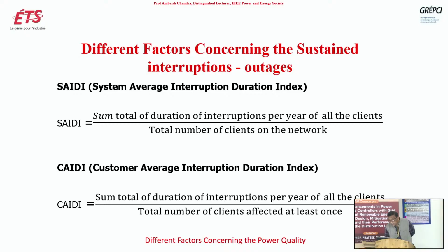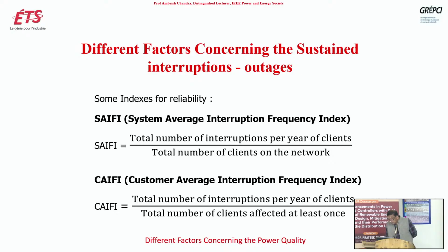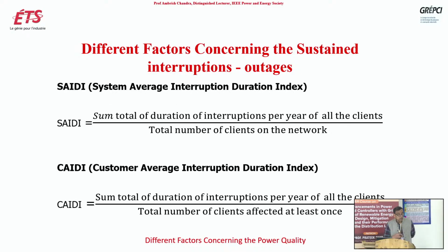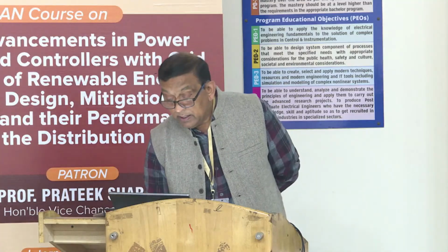Then we have SAIDI, System Average Interruption Duration Index. See, here we have the frequency, how many times, but SAIDI is about the duration, for how long. So SAIDI is the sum total of duration of interruptions per year of all the clients divided by total number of clients on the network. And CAIDI, Customer Average Interruption Duration Index. This is almost the same: the sum total of duration of interruptions per year of the clients. Maybe for 1 hour, 2 hours, 10 hours, there was no electricity. But here, the divisor is the total number of clients affected at least once. It is the same kind of difference we saw in SAIFI and CAIFI.